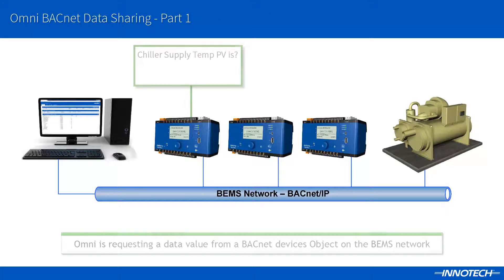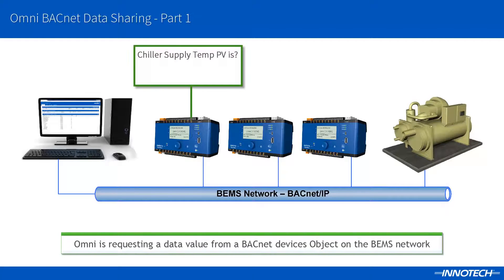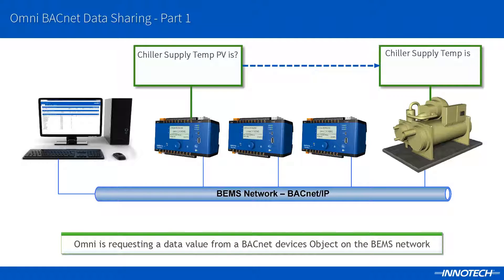BACnet data sharing essentially refers to a BACnet device requesting or writing data values to a BACnet object contained within another BACnet device on the network. For instance, in this example the OMNI controller is requesting the chiller's chilled water supply temperature value. The chiller, which has a BACnet over IP interface, responds back with the requested object's present value.